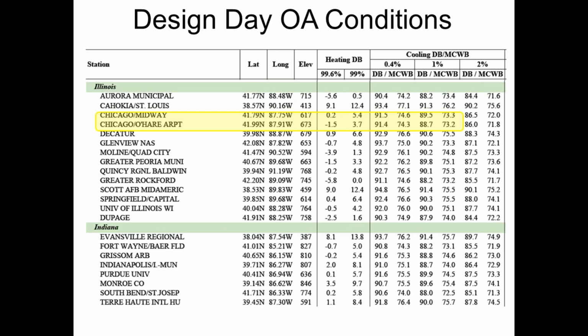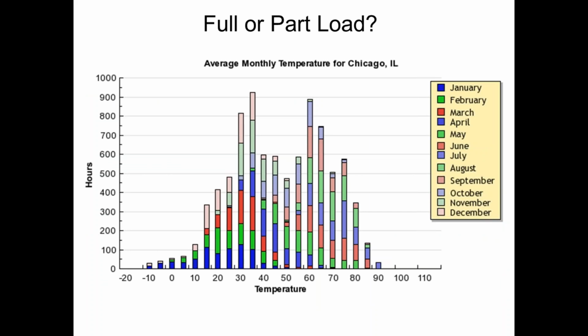And then if you're in some of the suburbs, like I live in Aurora, -5 is my heating design temp. But most of these are pretty similar to each other. And you're not going to find any that are 95 in Chicago area, and you're not going to find any that are -10 on the heating. So getting these outdoor temperatures right is one main component of getting these units sized correctly. Most packaged rooftop units are, in fact, oversized, as you probably know.